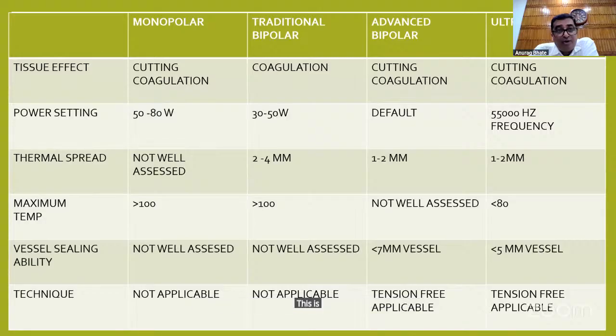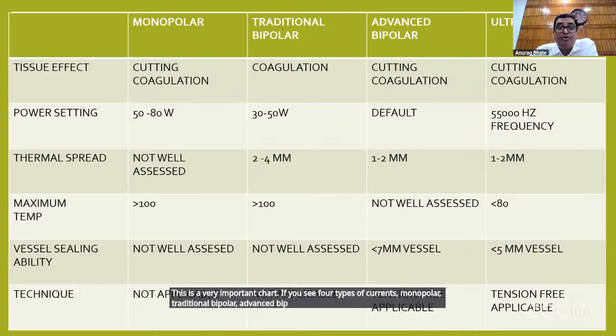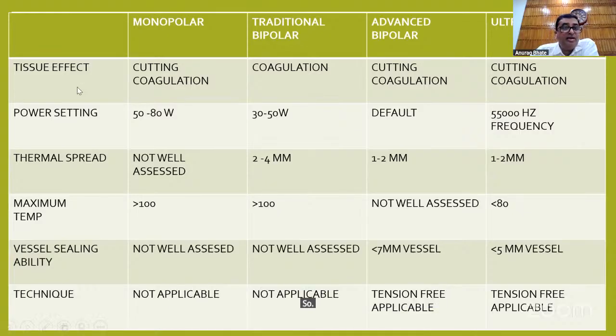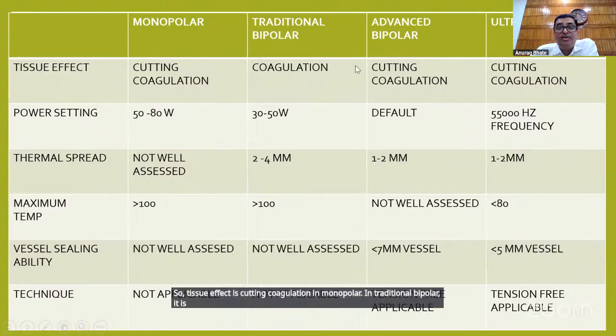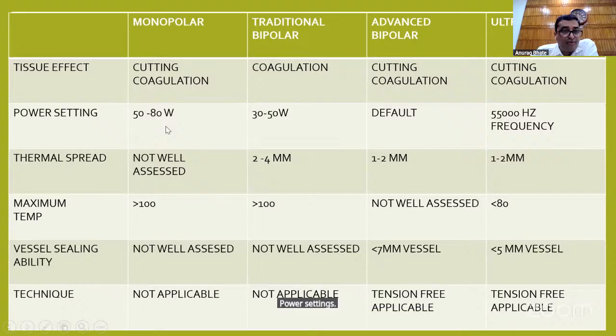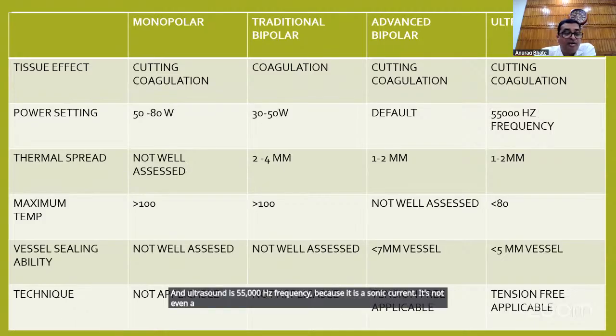This is a very important chart. If you see, 4 types of currents: monopolar, traditional bipolar, advanced bipolar, and ultrasonic bipolar. So tissue effect is cutting coagulation in monopolar. In traditional bipolar, it is just coagulation. In advanced bipolar, it is cutting coagulation, and in ultrasound, it is cutting coagulation. Power settings: monopolar 50 to 80, bipolar 30 to 50, advanced bipolar are default settings, and ultrasound is 55,000 hertz frequency because it is a sonic current. It's not even a current, it's an ultrasound related device.